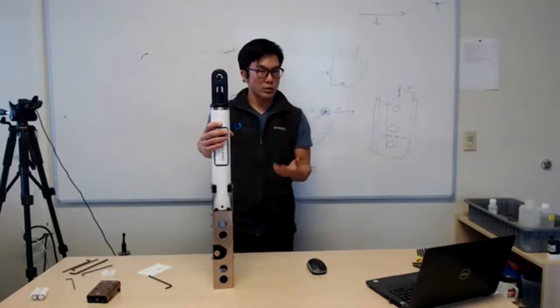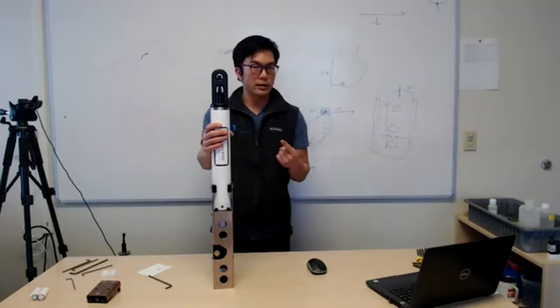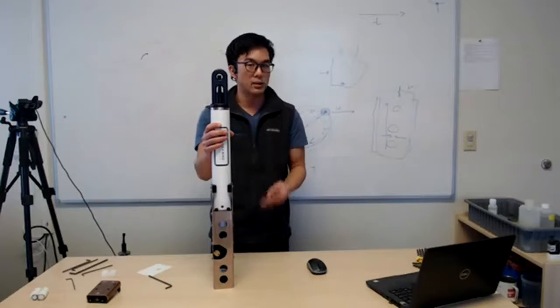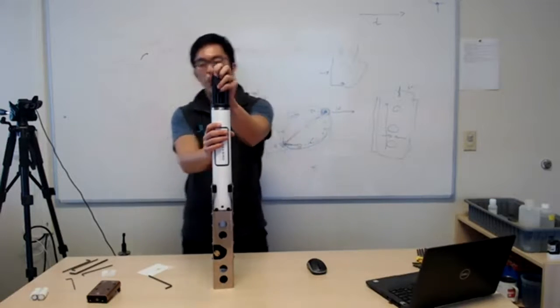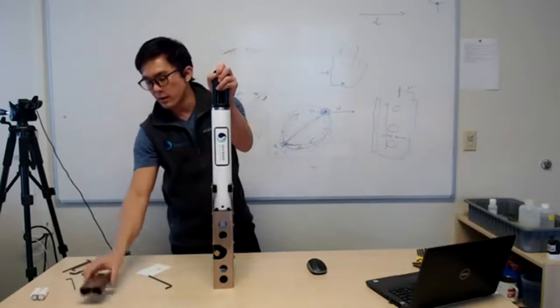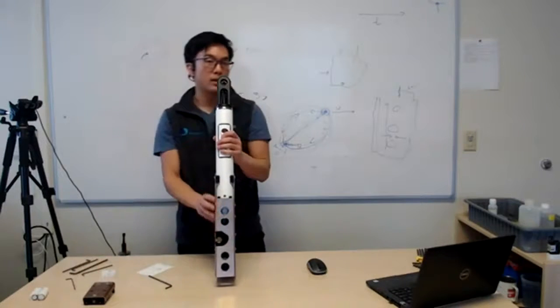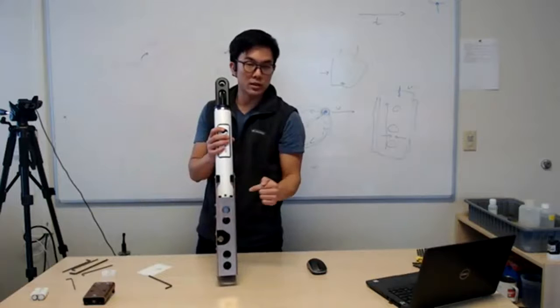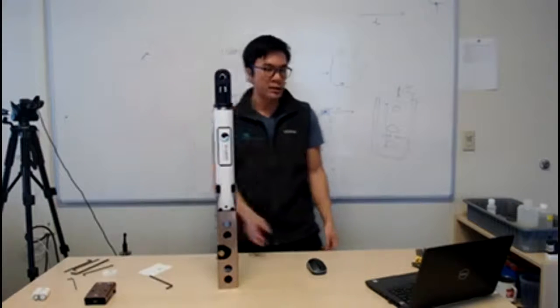And so for certain maintenance procedures, cleaning, flushing, pH calibration, conductivity checks, you're going to need to remove the antifouling guard so that you can attach Tygon tubing to these two hose barbs. We'll see that momentarily.